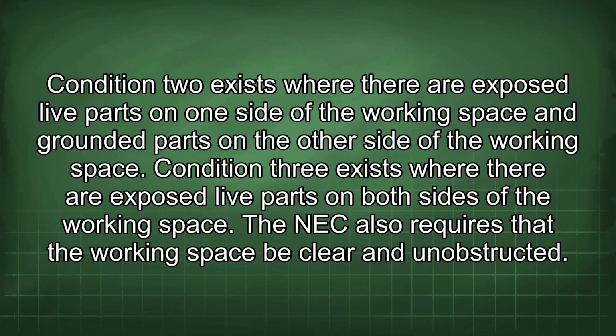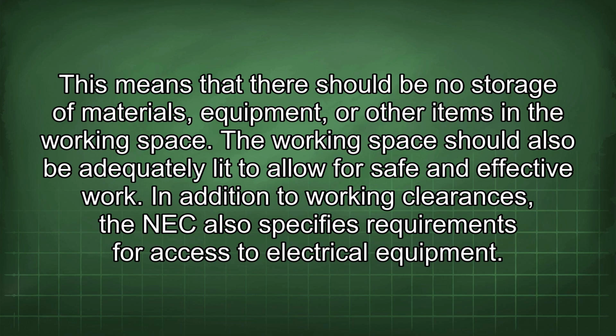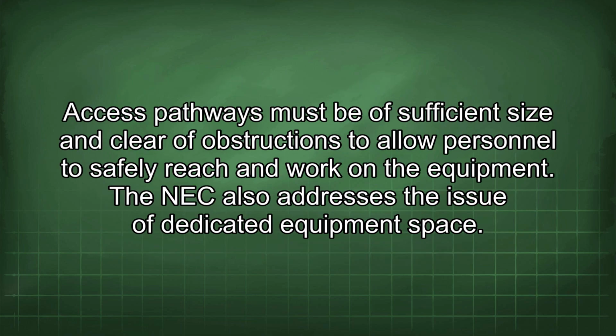The NEC also requires that the working space be clear and unobstructed. This means that there should be no storage of materials, equipment, or other items in the working space. The working space should also be adequately lit to allow for safe and effective work. In addition to working clearances, the NEC also specifies requirements for access to electrical equipment. Access pathways must be of sufficient size and clear of obstructions to allow personnel to safely reach and work on the equipment.